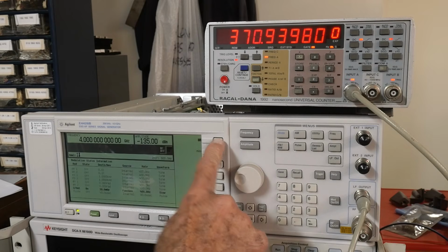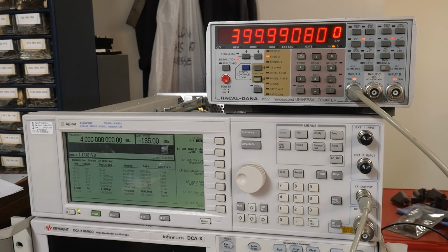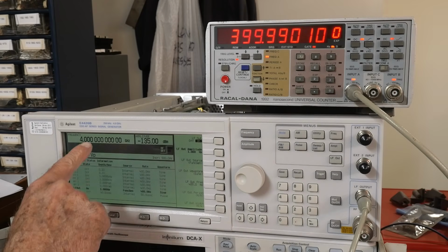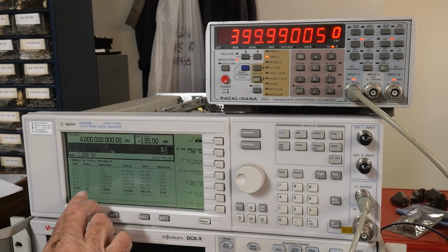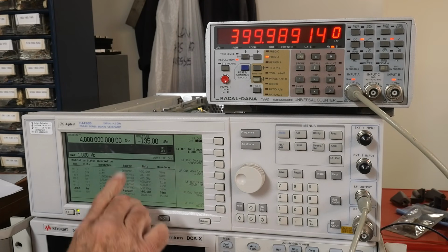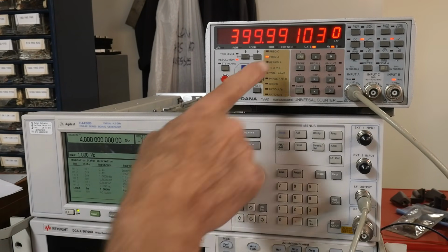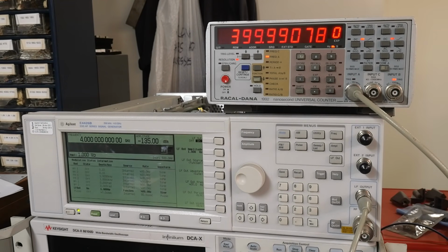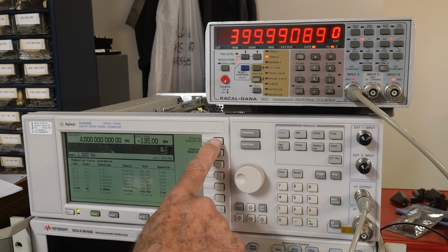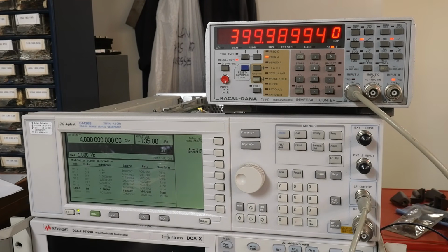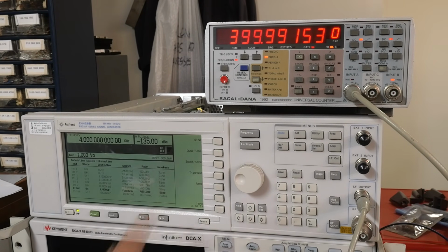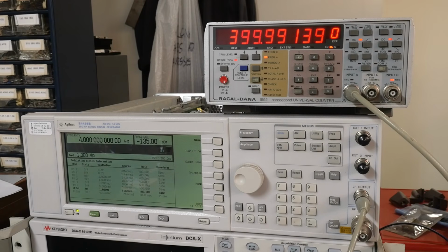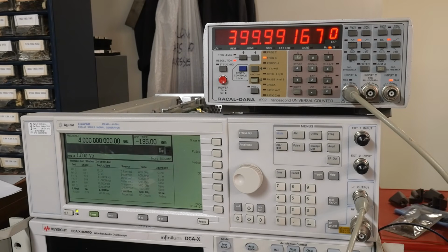But I want 1 volt peak to peak, so my frequency meter can read it. So, I have it set to LF output on 1 volt function generator source, 400 hertz sine wave. So the source can be the internal modulator or a function generator, kind of a generic function generator. So I have it set to function generator. And I have it set to sine wave, but it'll do dual sine, so two-tone, swept sine, triangle, and ramp, and square pulse noise and DC. All right, so sine is good.